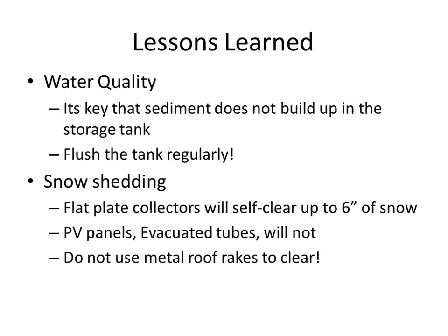Water quality, probably most of the dissatisfaction I've seen with these systems comes from homes that haven't addressed intrinsic water quality issues. On city water, I've yet to see this be a problem anywhere. But with well water, there's very, very high mineral content, and what we're seeing is sedimentation in the heat exchanger and storage tank at a pretty rapid rate.